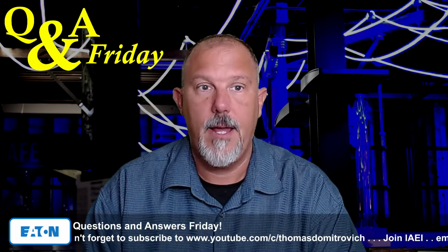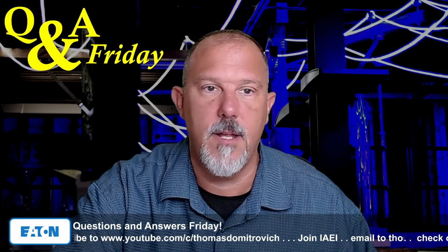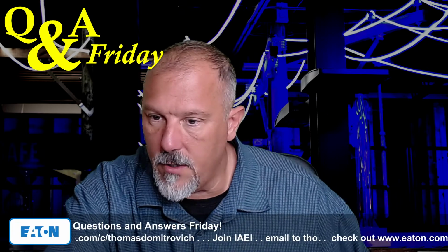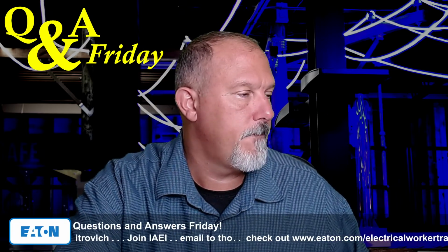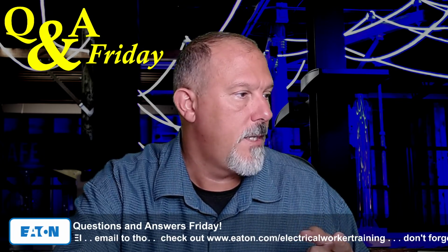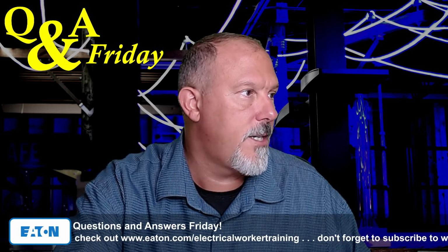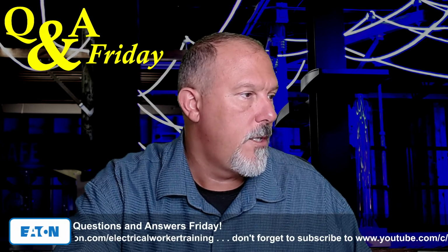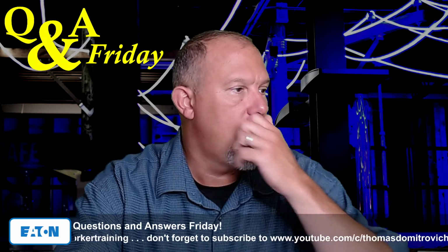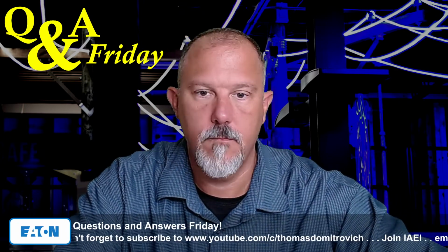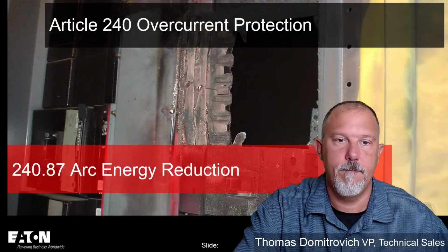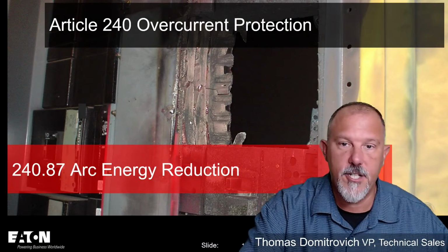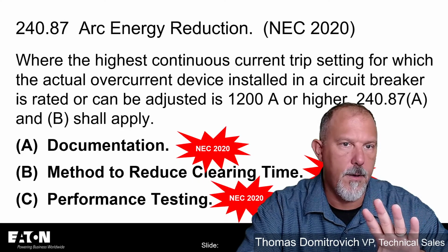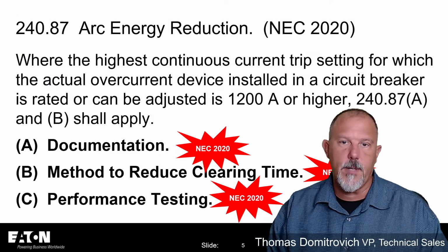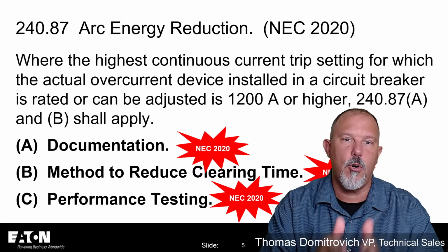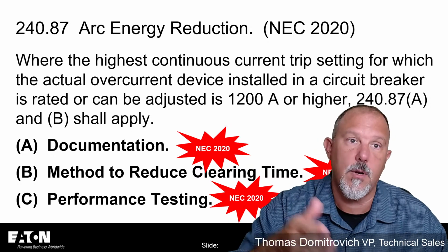Now, 240.87 has a couple requirements, and I'm just going to call up my 240.87 presentation, and I do have a hard stop in less than 10 minutes, at 1 o'clock. NFPA 70, I'm going to grab the 2020 code. Arc energy reduction. All right, so here's what it says in the 2020 code. Where the highest continuous current trip setting for which the actual overcurrent device installed in the circuit breaker is rated or can be adjusted is 1200 amps or higher.